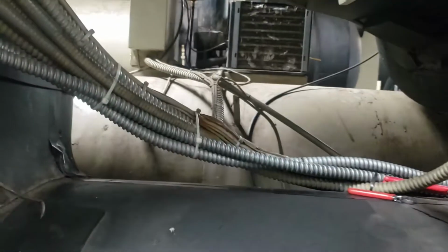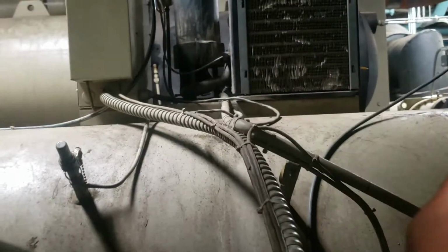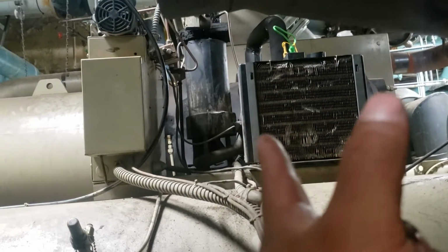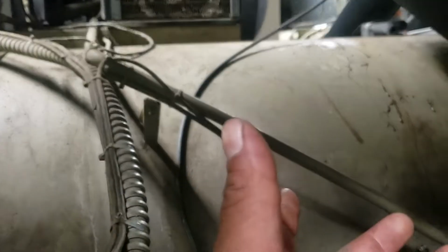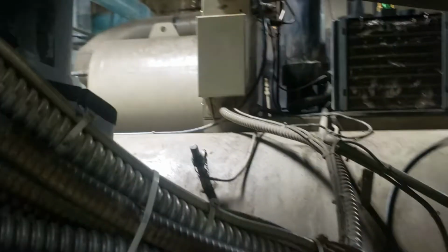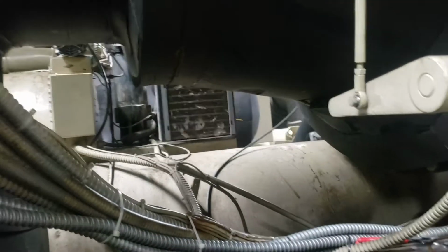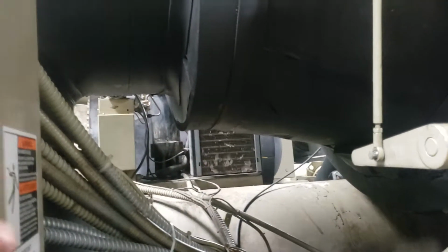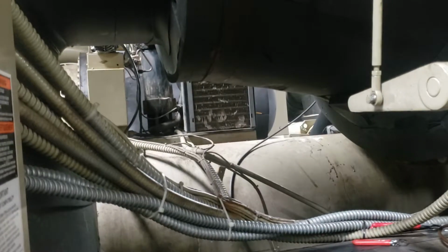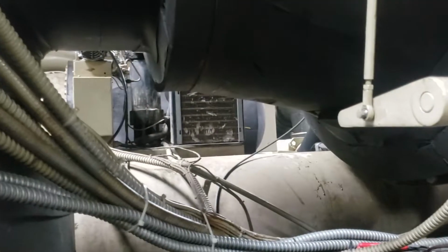These two shut-off valves, that way I don't have any vapor going into my purge tank. Without the warmer vapor going into the purge tank, eventually that evaporator will start getting cold, because there's no warm refrigerant going through it. There's no heat to absorb, so the temperature is going to start dropping. It's going to act kind of like air in that tank, so there's no heat transfer.